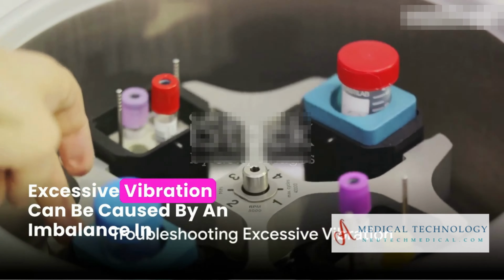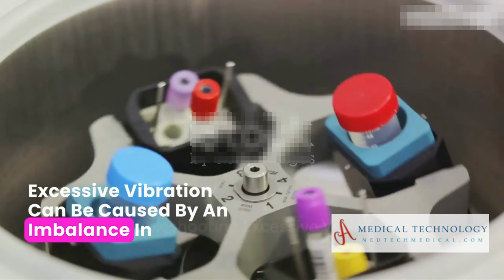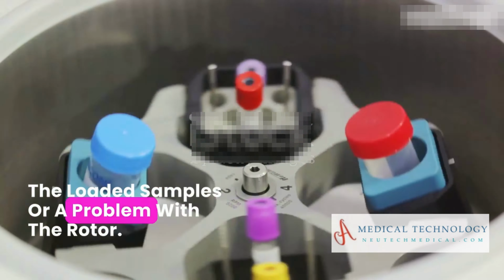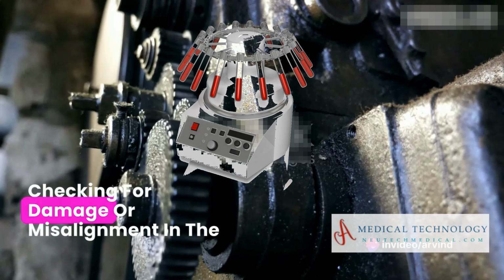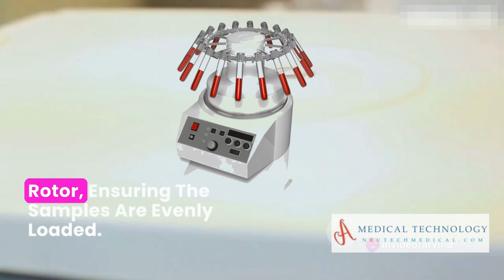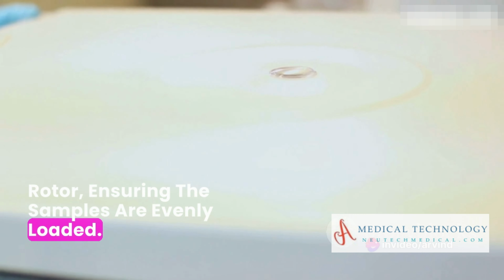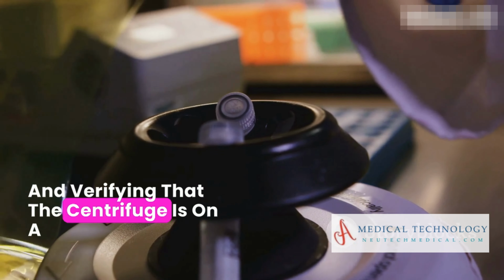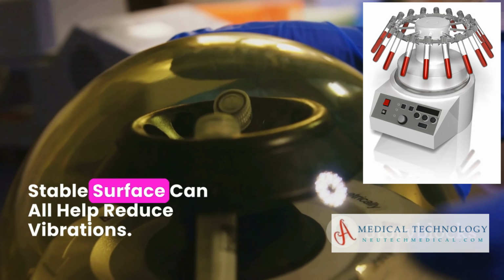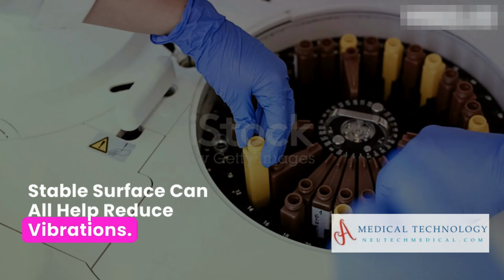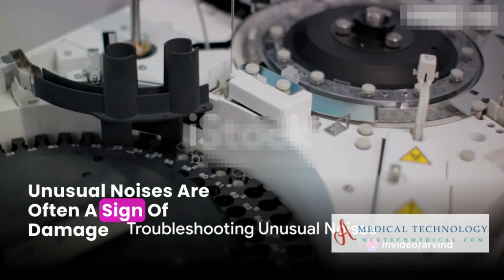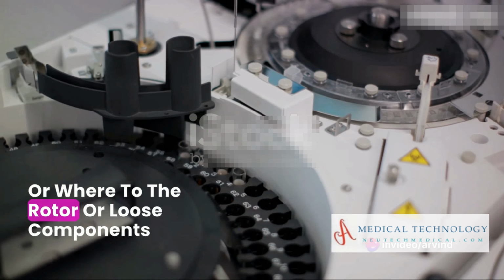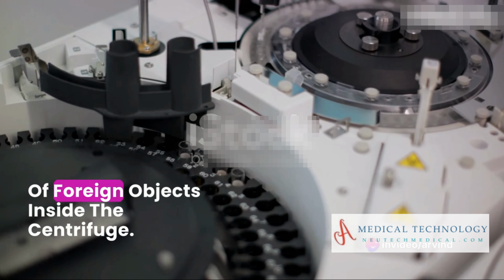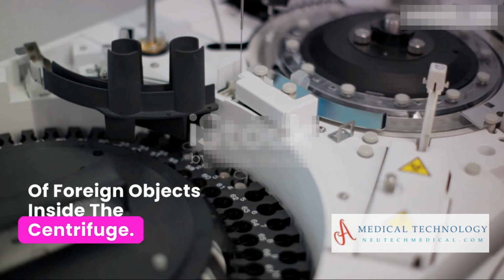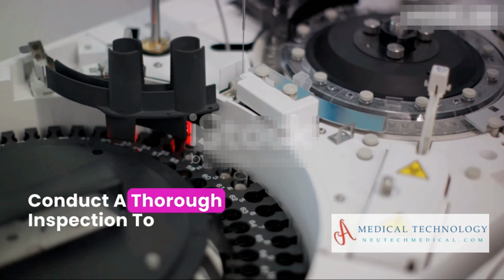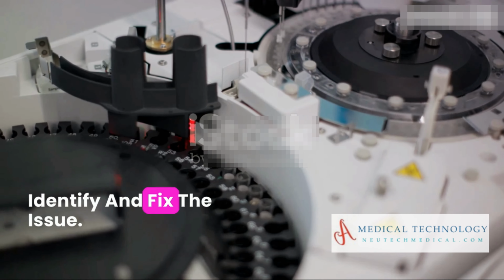Excessive vibration can be caused by an imbalance in the loaded samples or a problem with the rotor. Checking for damage or misalignment in the rotor, ensuring the samples are evenly loaded, and verifying that the centrifuge is on a stable surface can all help reduce vibrations. Unusual noises are often a sign of damage or wear to the rotor or loose components or foreign objects inside the centrifuge. Conduct a thorough inspection to identify and fix the issue.